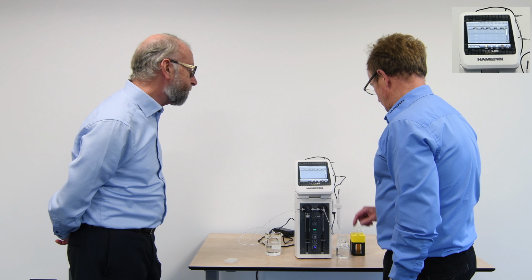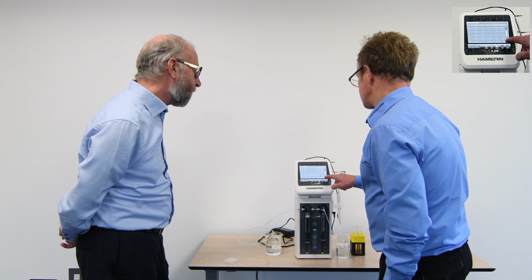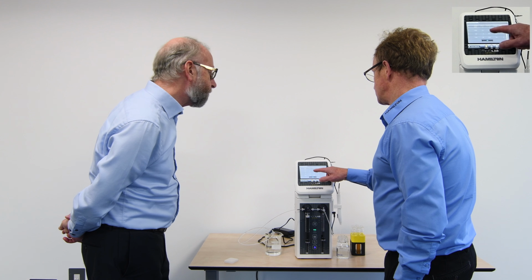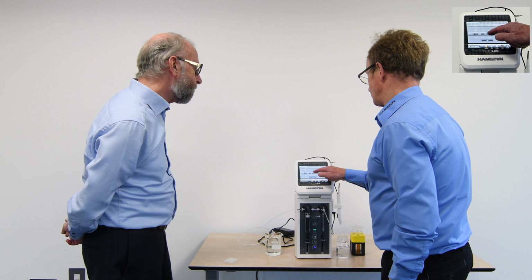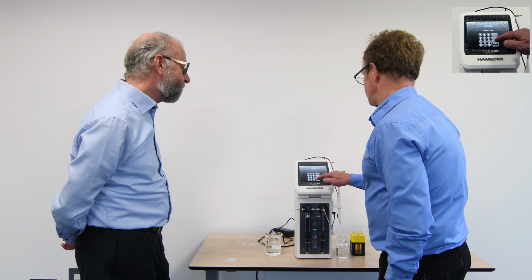So in your step, if you wanted to change that diluent volume to a higher ratio dilution, we can go to that step, which we can see was at the end here. So just scroll through. And we can see it was automatically aspirating here 5,000 microlitres. If I wish to, now I can highlight that volume and change that to 10,000 microlitres. I've gone in and entered that as a figure, and we can change the volume here.